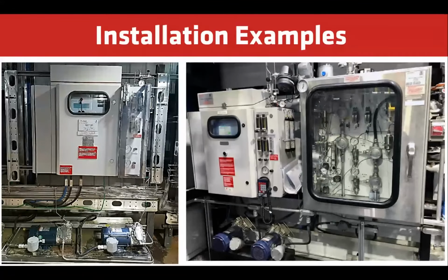Installation examples. You can see a couple of different designs, with sample conditioning on the right side in a different enclosure, whereas on the left side it's a standalone, where the sample comes in directly to the analyzer. We generally recommend 2 vacuum pumps, and you can see there are 2 vacuum pumps in both applications. Typically, one vacuum pump is in standby mode while the other is operating. When it comes to your quarterly or 6-month replacement of the diaphragm, you simply turn the other vacuum pump on and take the first one out of service so you can do the maintenance. This prevents you from having to do a maintenance shutdown on the analyzer to repair the pump.